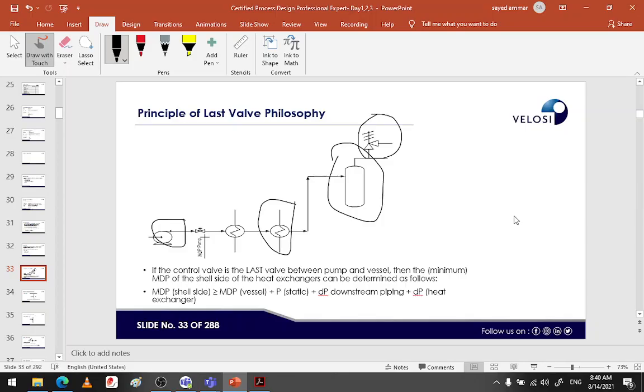In this, there is no point to design for shut-off pressure because there is no valve downstream of the heat exchanger. Yes, this is a typical BFD, but in a normal BFD, there will be category 2 valves for the heat exchanger for maintenance purposes. The question, doctor, here, why not design for the shut-off pressure of the pump? We are going to design for the shut-off pressure of the pump.